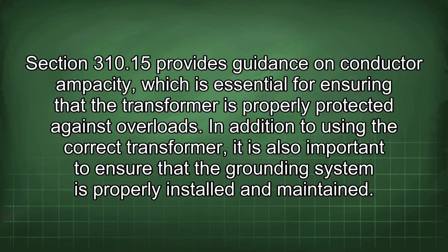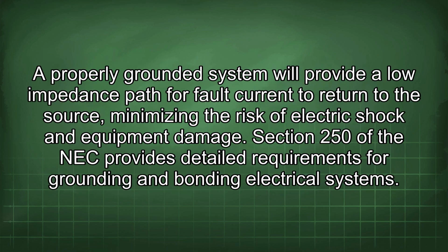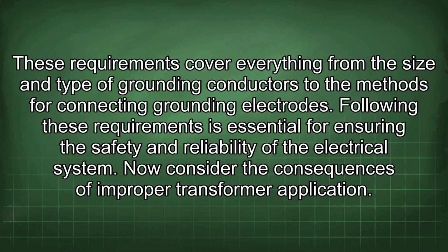In addition to using the correct transformer, it is also important to ensure that the grounding system is properly installed and maintained. A properly grounded system will provide a low impedance path for fault current to return to the source, minimizing the risk of electric shock and equipment damage. Section 250 of the NEC provides detailed requirements for grounding and bonding electrical systems. These requirements cover everything from the size and type of grounding conductors to the methods for connecting grounding electrodes. Following these requirements is essential for ensuring the safety and reliability of the electrical system.